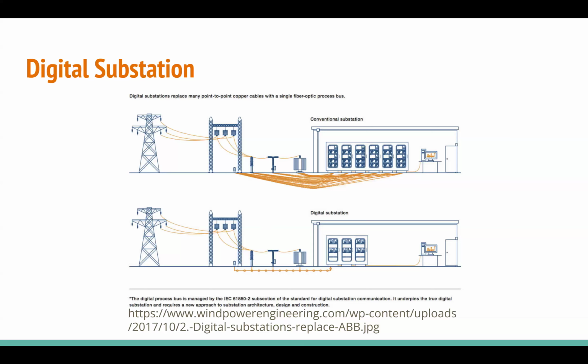That's actually a really good thing, because that means we have our different monitoring equipment in the conventional substation. A long time ago, that would have been electromechanical relays; now we use microprocessor-based relays. Because we have these primary values and then secondary values, we can run our secondary values into the substation or control house, where a user can work with them directly. These values are much less dangerous to work with, but also easier for your equipment to work with. Let me jump back a couple slides and come right back here.